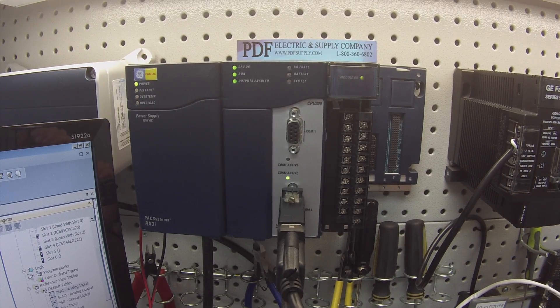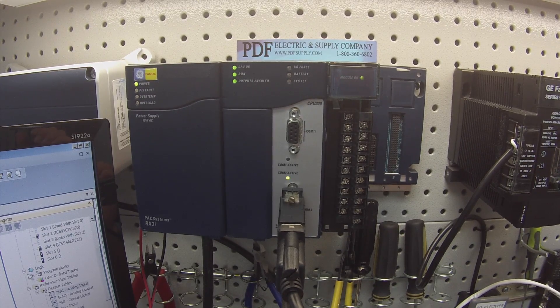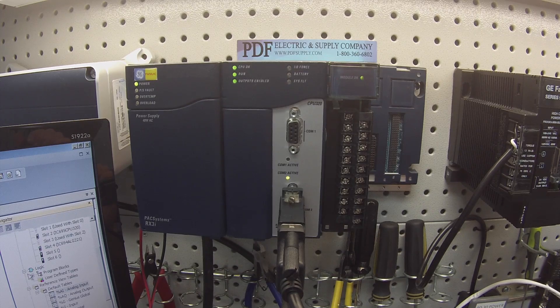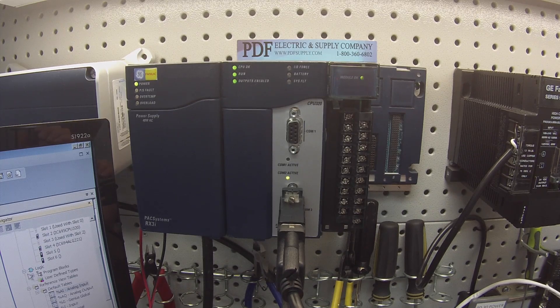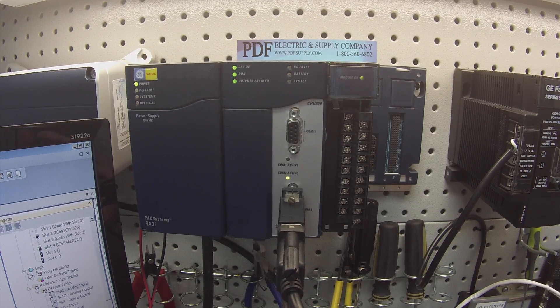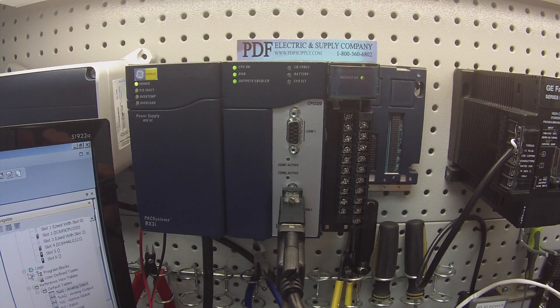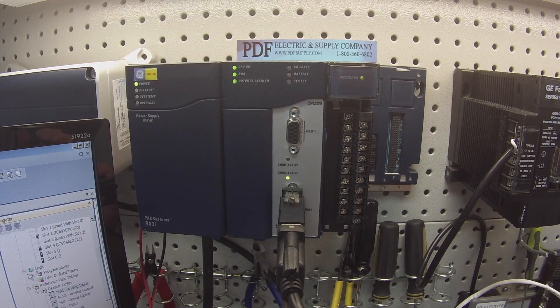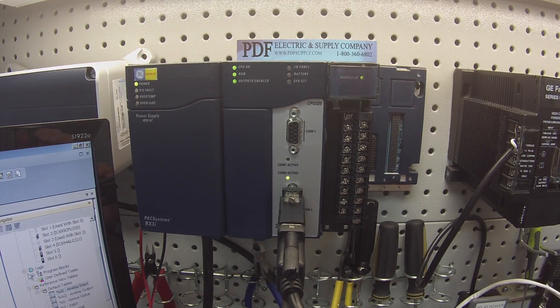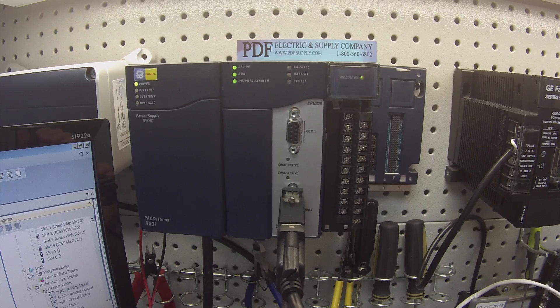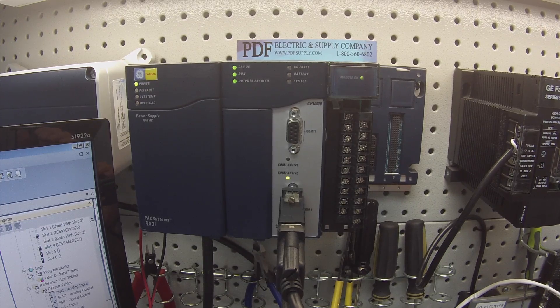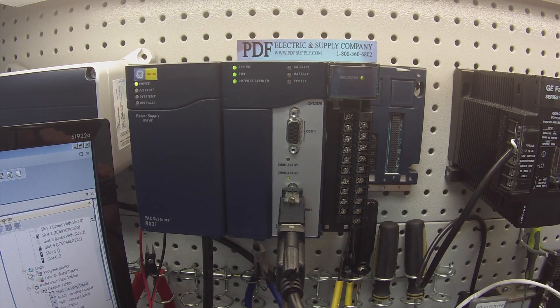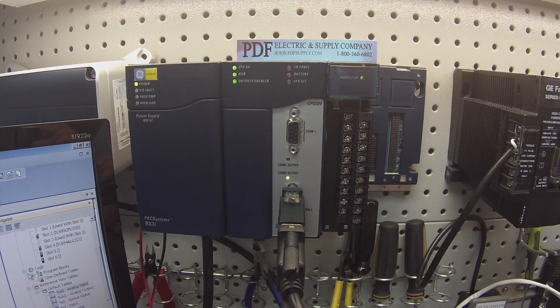Check for channels that fail at full value, 32,767, that doesn't move up or down when you manually move it up or down with your 4 to 20 milliamp generator. Also check for fluctuating circuits, circuits that are not stable. Any of those three things, and you have a bad module that needs replacement or repair.